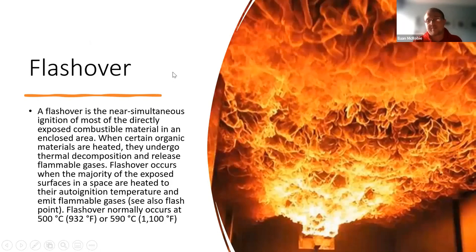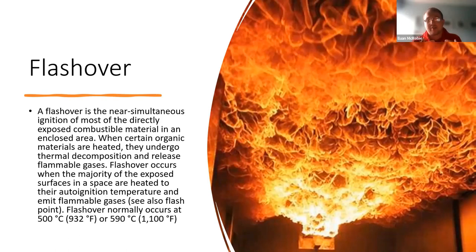Flashover is when a compartment has exposed every combustible material within that area to its ignition temperature, and all the thermal gases in the upper layer ignite, resulting in a fully enveloped fire within the compartment. Temperatures can reach 500 to 590 degrees centigrade — you're not going to survive that. It's one of the biggest risks to fire wardens and firefighters, and we want to mitigate this occurring in homes and commercial premises.